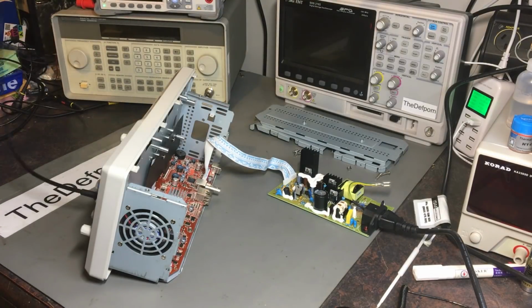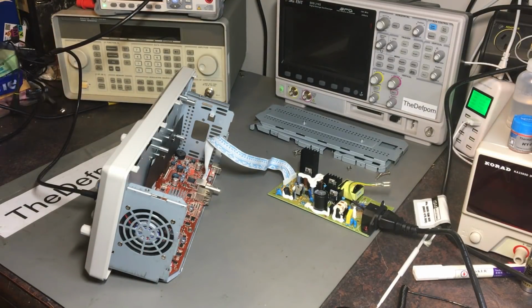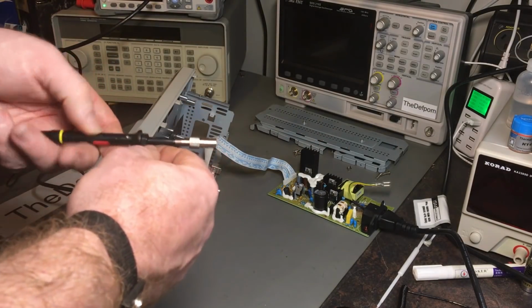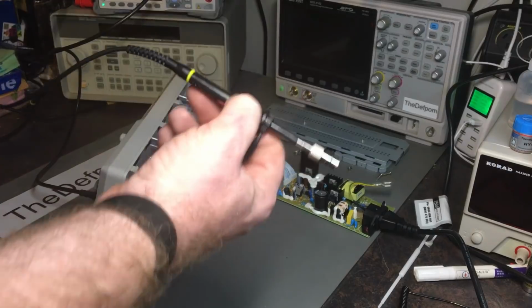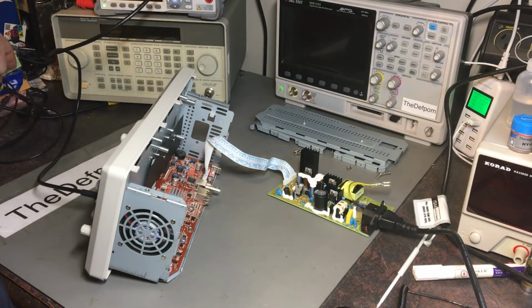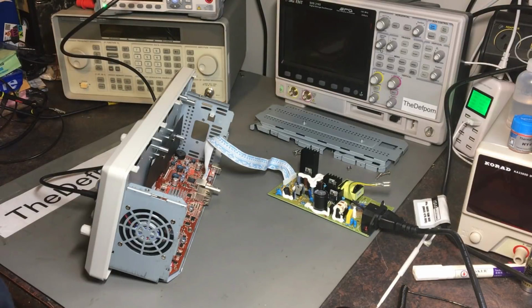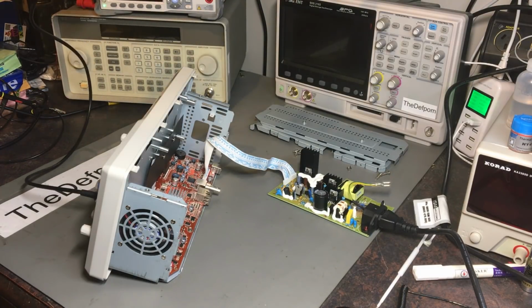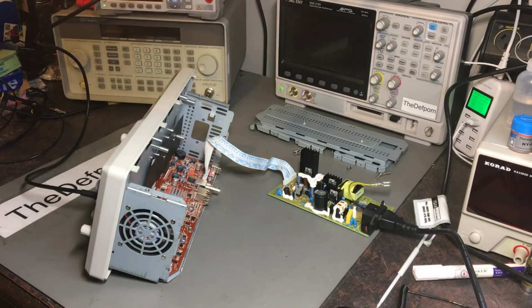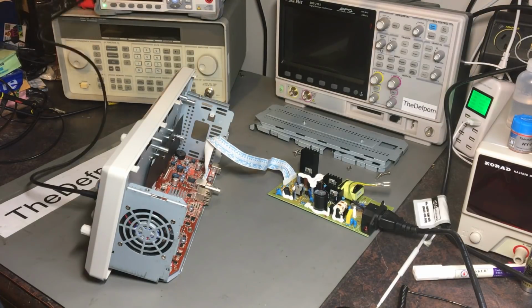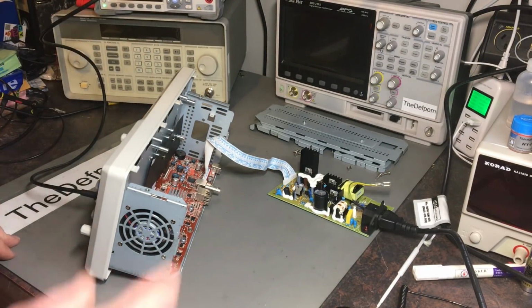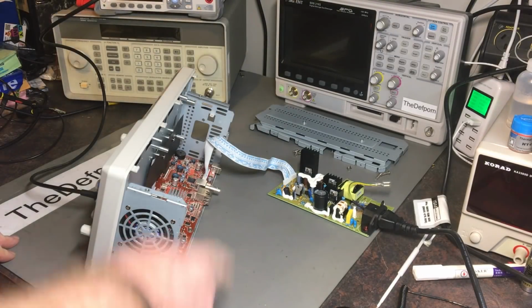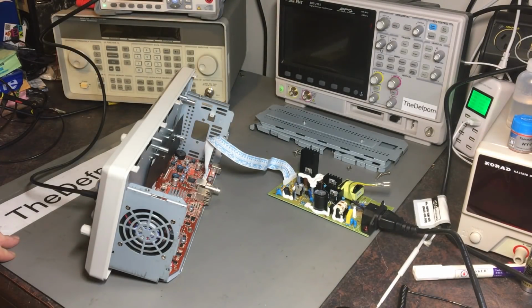Now I've used a BNC cable, because as I showed at the very beginning, the scope probe, whilst it works and gives you a nice response, the rise time is a bit slow, even though it's set at 1 times. So it's obviously having a capacitive effect on the input. So the recommendation from Rob is to just use a BNC cable. And what I saw when I used this BNC cable is that the rise time is much faster and there's a little bit of ringing there. So as long as I watch out for the ringing not fooling me, the rise time being fast at least gives you a chance to actually see what's going on rather than being hidden by the rise time. Okay, because you're on a nice sharp corner on that square wave.